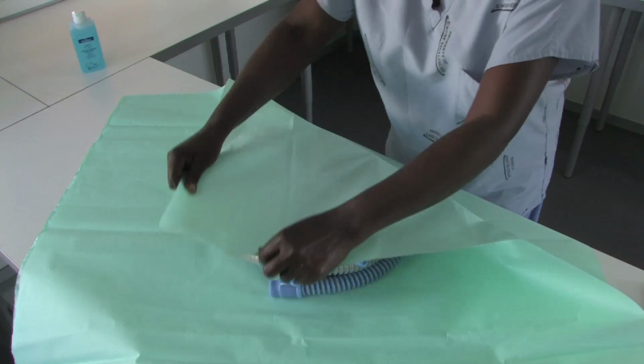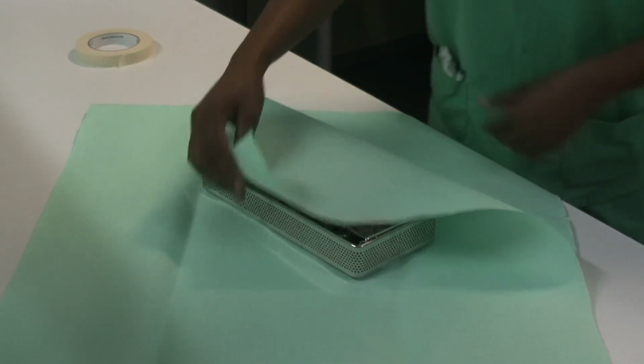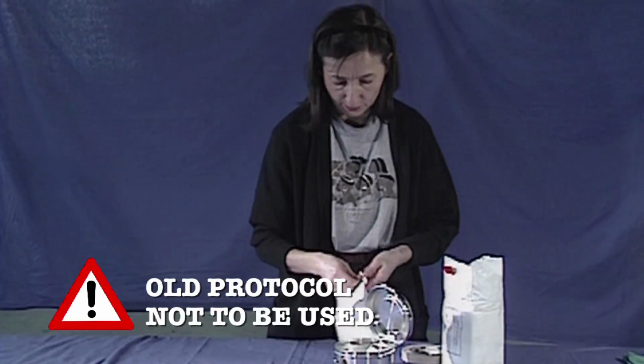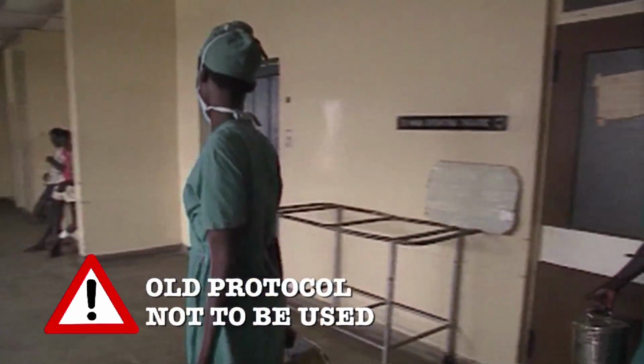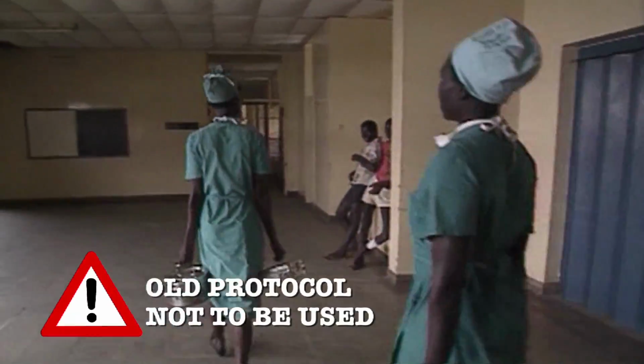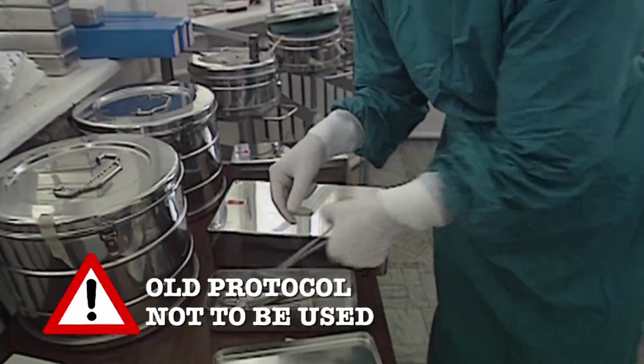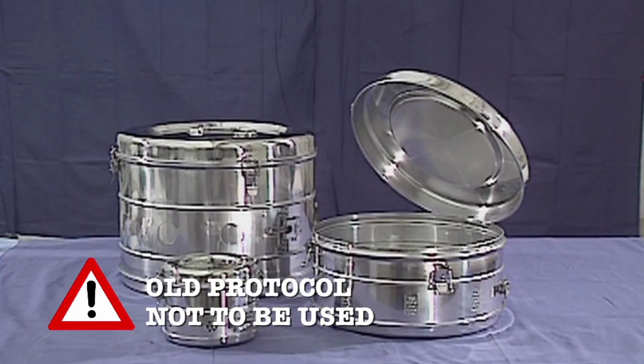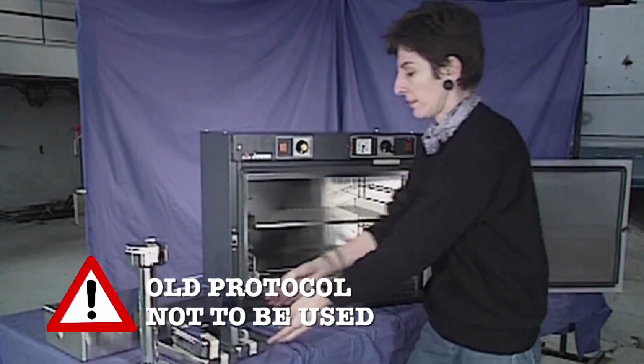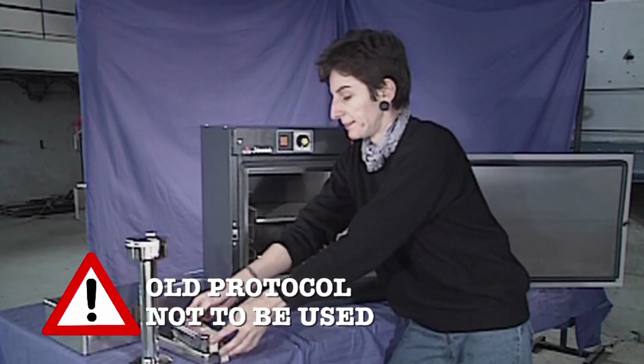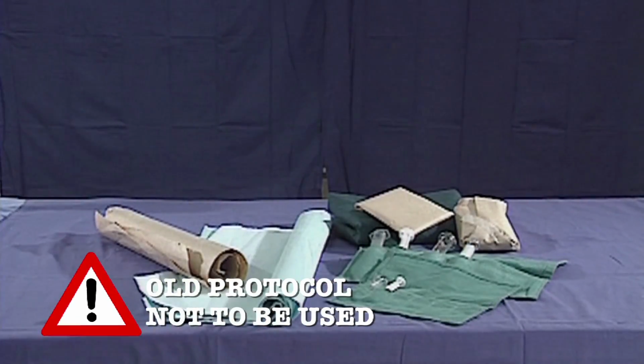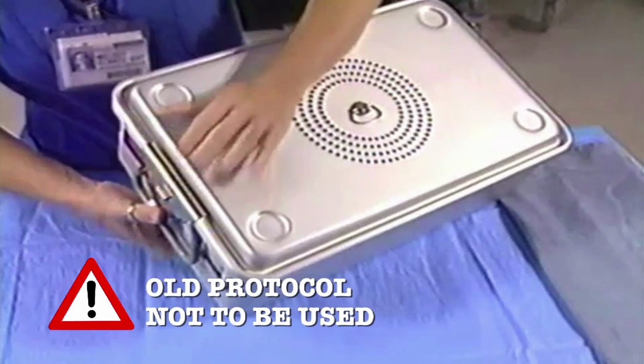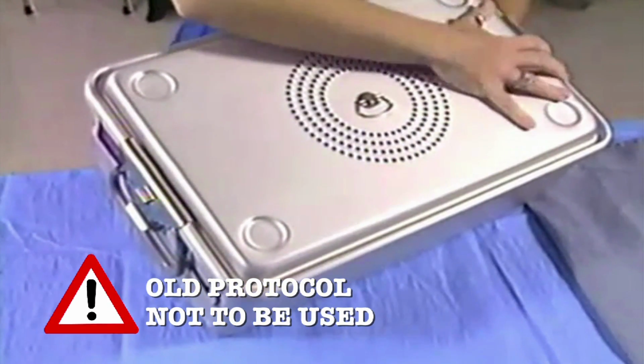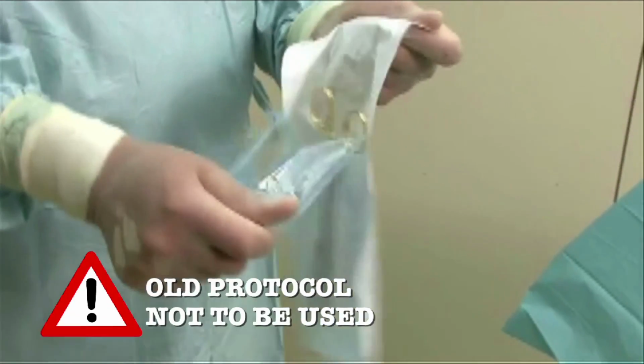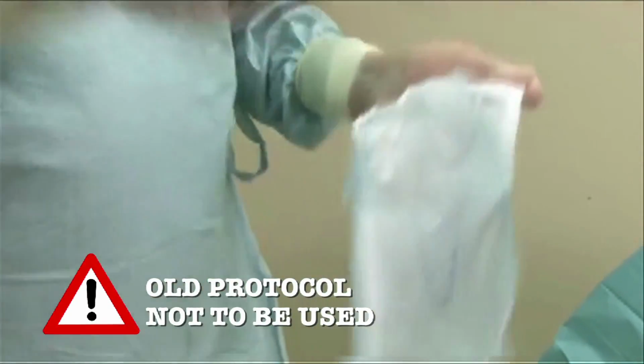It's important to use packaging appropriate to the autoclave available in the field. Some packaging materials are now obsolete and should not be used with the autoclaves on MSF projects because they do not keep things sterile. This is true of drums, the stainless steel boxes that were used in Pupinel dry heat sterilizers, kraft paper and cotton drapes. While sterilization containers, pouches and tubing are very good, more modern packaging materials, they're not appropriate for the autoclaves currently used on MSF projects.